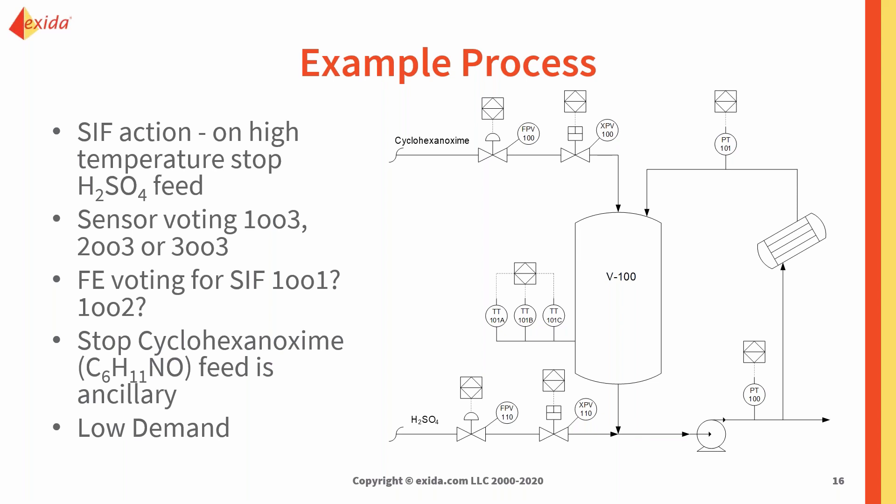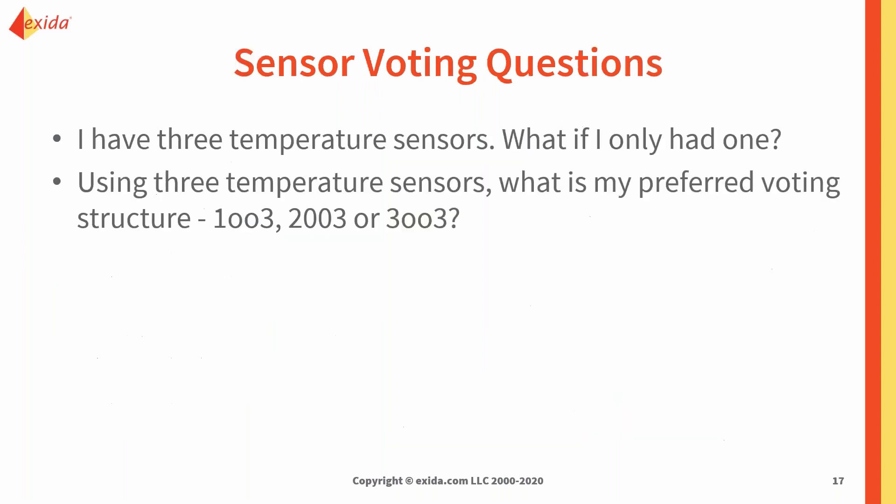We also have on our final elements an XPV in the sulfuric acid line — an on-off valve attached to the SIS — and an FPV, a control valve primarily used for control in the basic process control system. We'll look at whether the FPV can also be used to help support the safety interlock. We are operating in low demand mode. With the three temperature sensors, we'll first look at what if we only had one, then decide if we need to use the redundancy of three and what the appropriate voting would be.